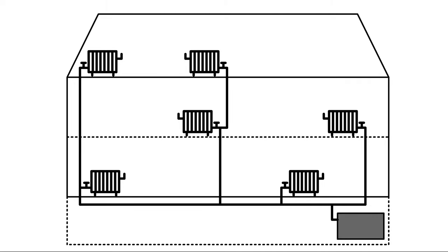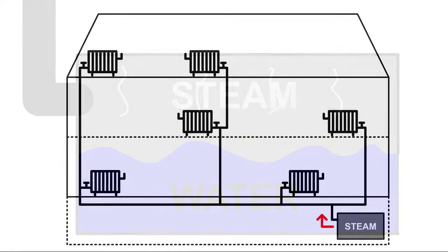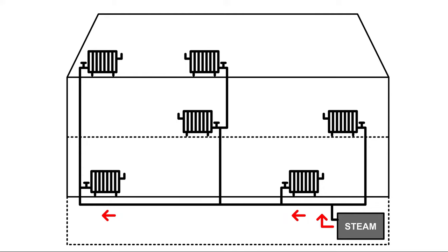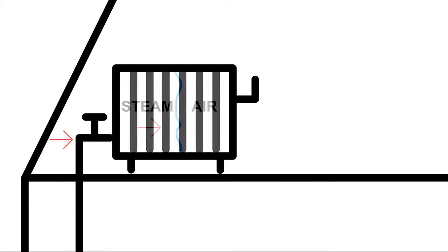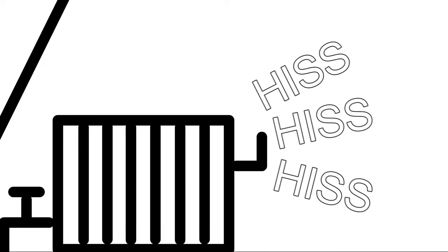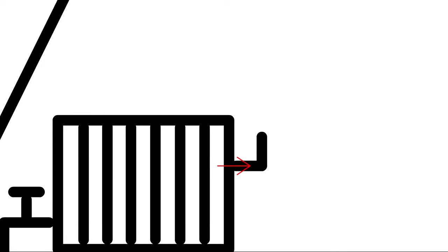Let's start with a primer on single-pipe steam radiator systems. Somewhere in a basement or crawl space, you have a boiler, which is turning water into steam. When water gets turned into a gaseous state, or steam, it wants to expand, which is a very handy property that brings heat through a series of pipes to your radiators.